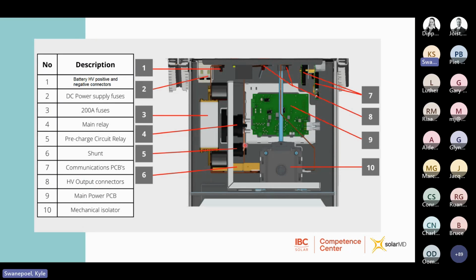Your main PCB, this is your power PCB, which will essentially handle the DC to DC conversion for the power supply to the control boards over here. It also supplies the relay and the sensors, for instance, on the mechanical isolator as well. And then number 10 is your mechanical isolator. And then here at the back, you just have a heat sink for dissipating any heat.